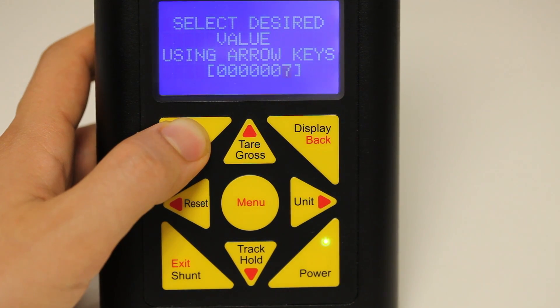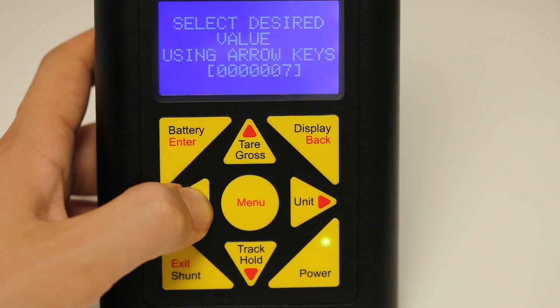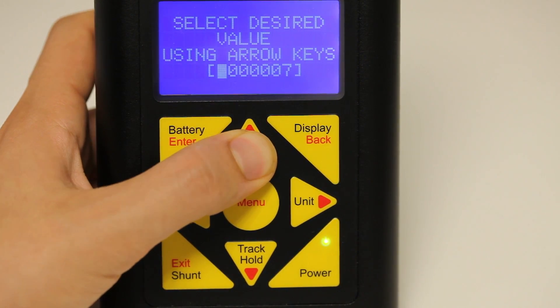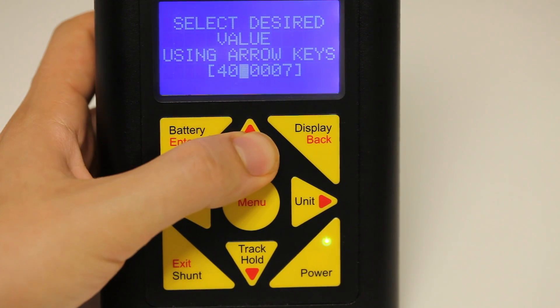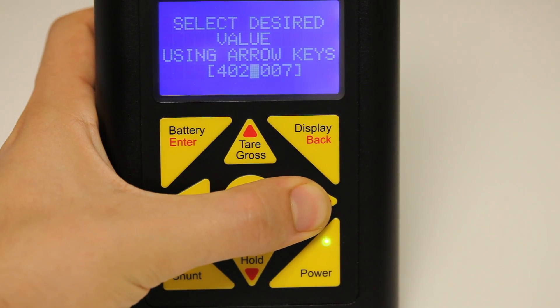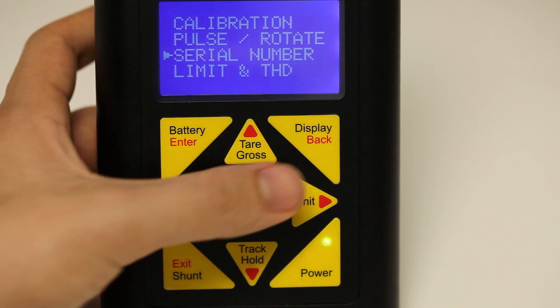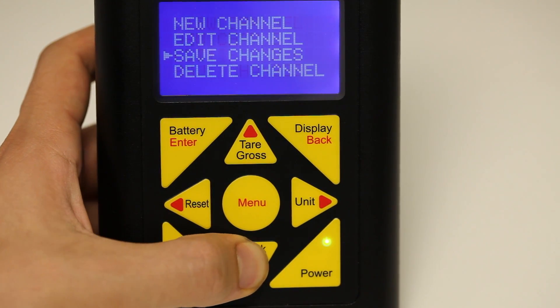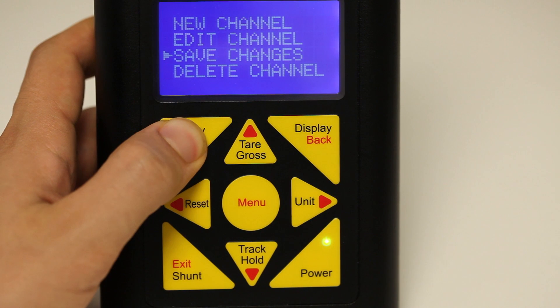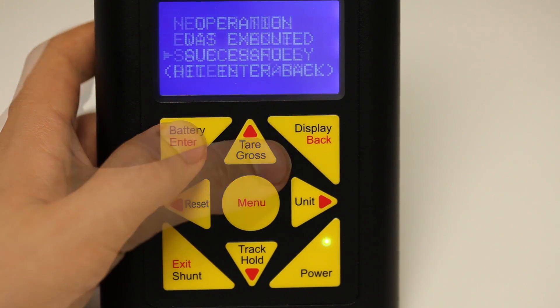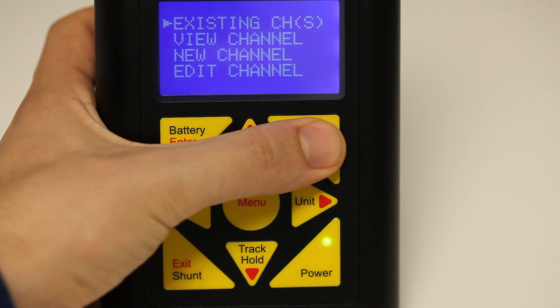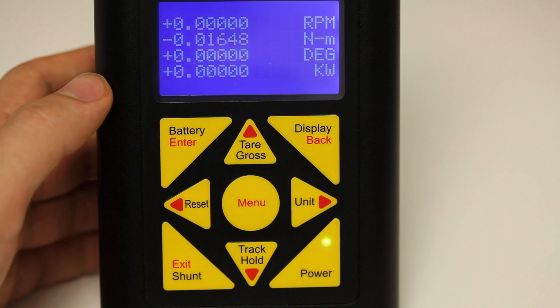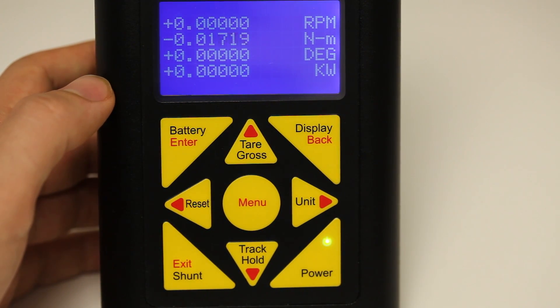Go into the serial number. Here, you can set your sensor serial number or another number that helps you understand that this profile relates to your load cell. For our example, we will set it to the sensor serial number, which is 402082. Now, press the red back button to exit out to the profile menu. Using the down red arrow key, cycle down and highlight save changes. Press enter to save changes. Hit the back red button to exit out to the main menu, and again hit the back button to go out to the regular menu. This completes how to set up an IHH500 profile.